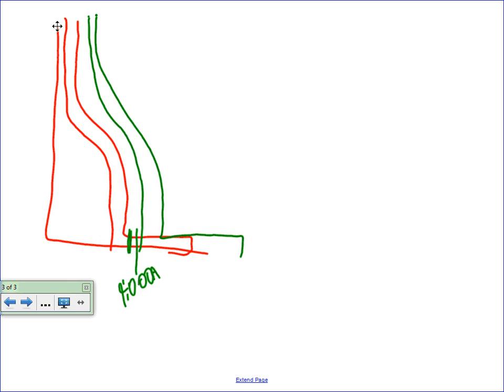Now, in the hospital, we're probably talking much bigger fault currents than that, so now we'll start looking at solid state breakers, which is a microprocessor based breaker that has CTs internal to it and a trip unit that you can actually have potentiometers to adjust the trip curve on the breaker. So now this solid state breaker, 400 amp, we can adjust long time. If it's a 400 amp breaker, we can dial it down to 0.4. So we can dial it down to 160 amp breaker up to 400 amps.